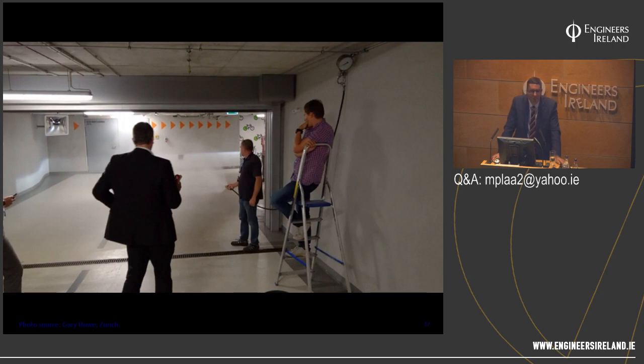So we're in a high challenge, high fire load underground car park with difficult firefighting access and egress, and the contractor hasn't proven the system is fit for purpose. So I asked the important question, well, I need to test it. I want that proven. And when it was proven, most of the systems actually failed their water delivery discharge times to get water to the point of delivery.